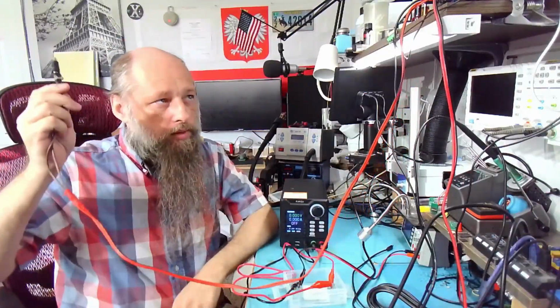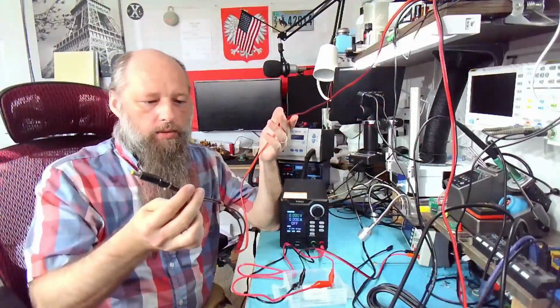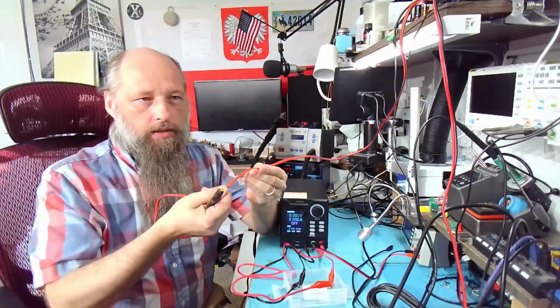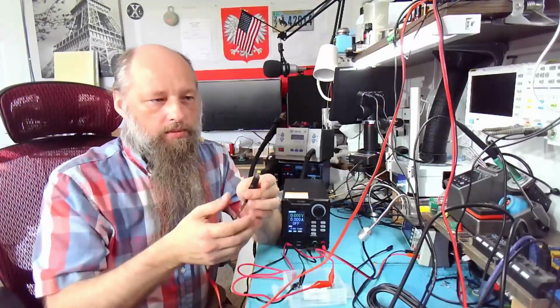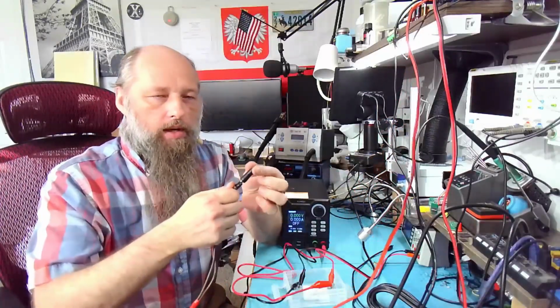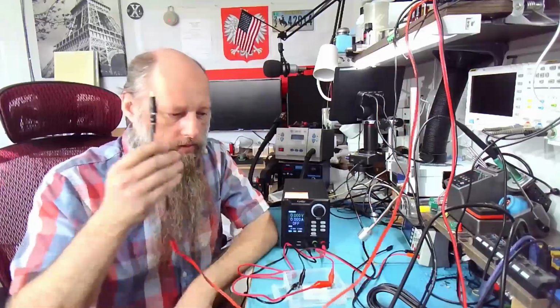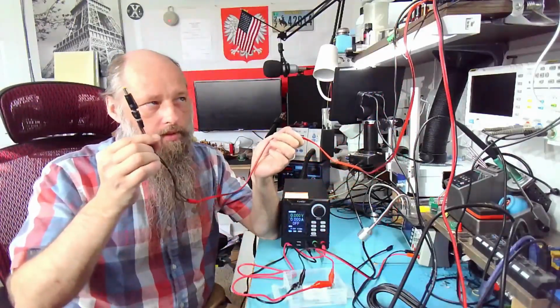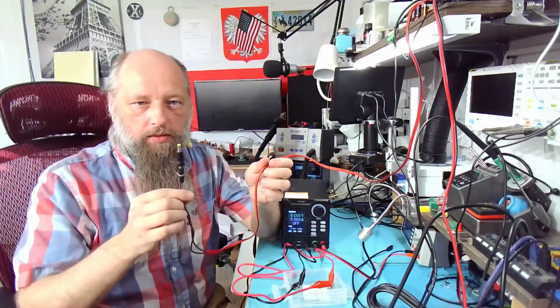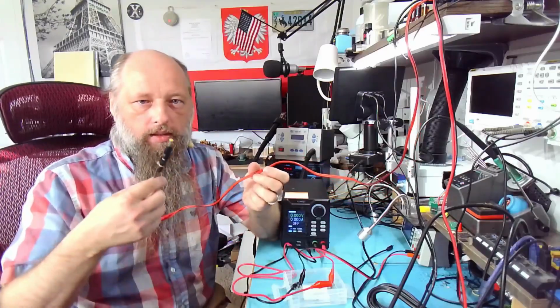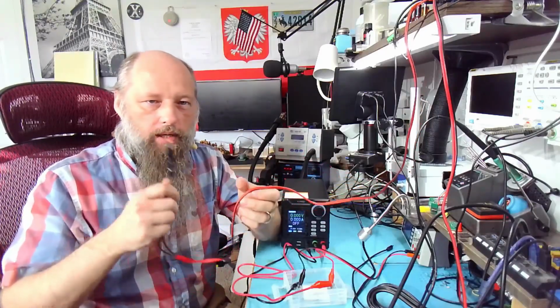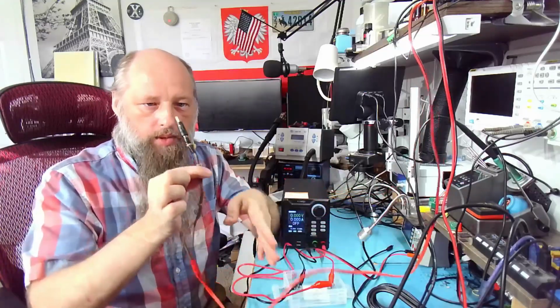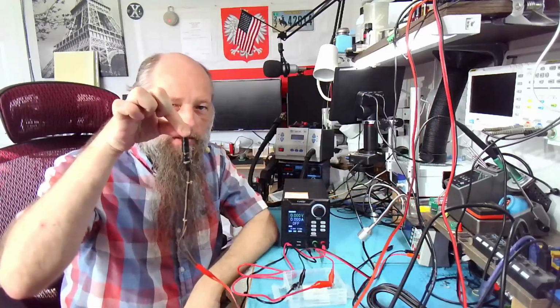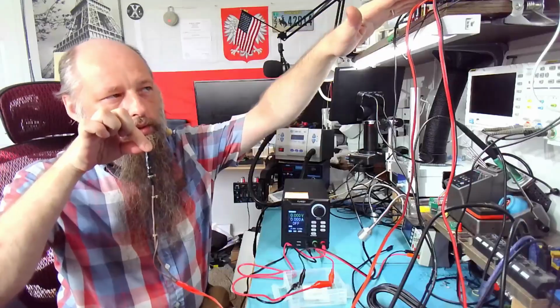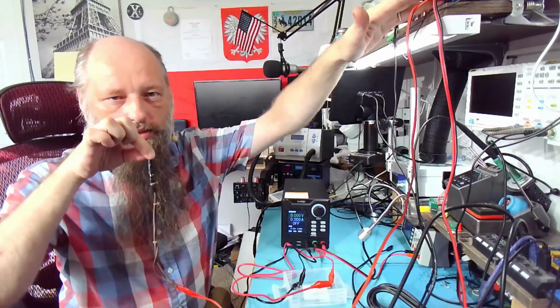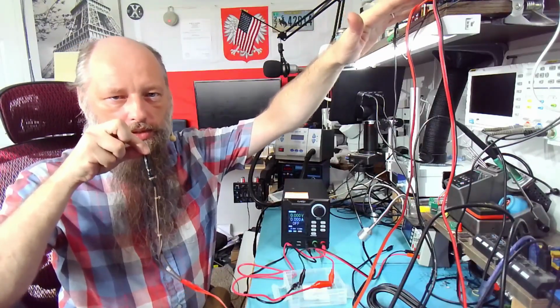So you have to consider how long your cable is, what's the gauge on the wire, and sometimes the cleanliness of the plugs themselves. I know that on this wire I have a drop of 150 millivolts, so if I need exactly 19.5, I put 19.65, because at that point I will have 19.5, but the meter or the power supply on that side is reading 19.65.